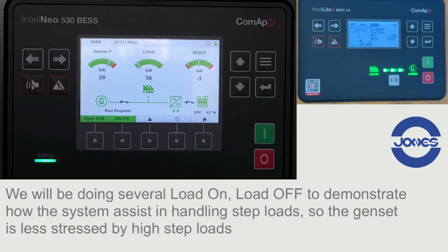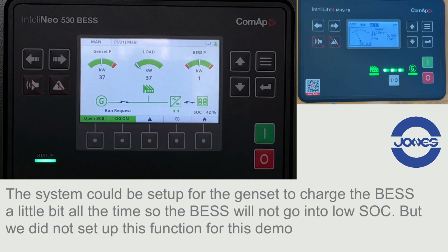We will be doing several load on, load off to demonstrate how the system assists in handling step loads, so the genset is less stressed by high step loads. The system could be set up for the genset to charge the BESS a little bit all the time, so the BESS will not go into low SOC, but we did not set up this function for this demo.